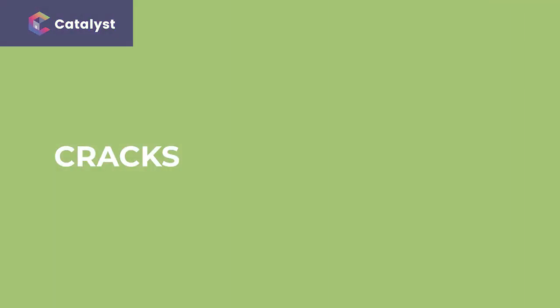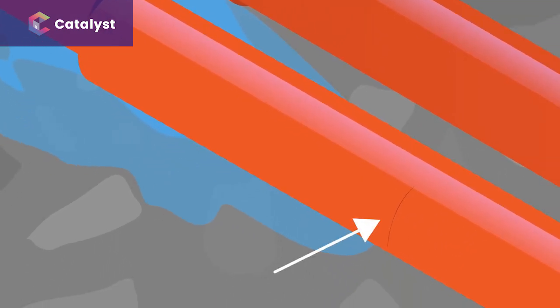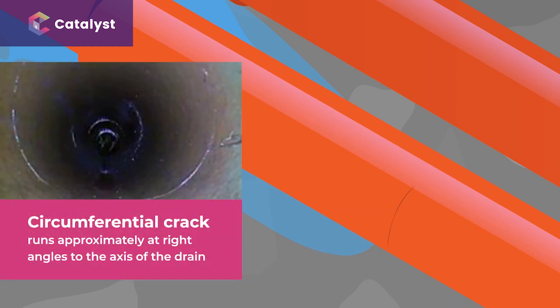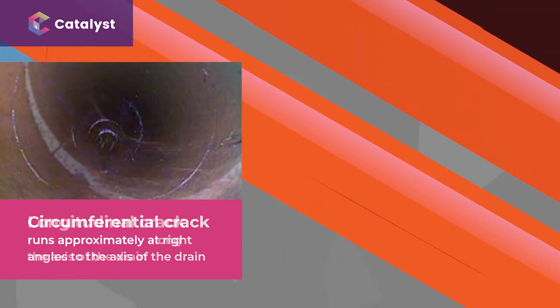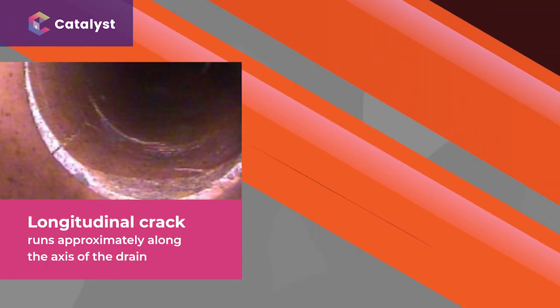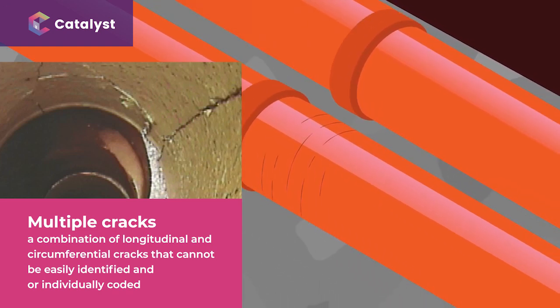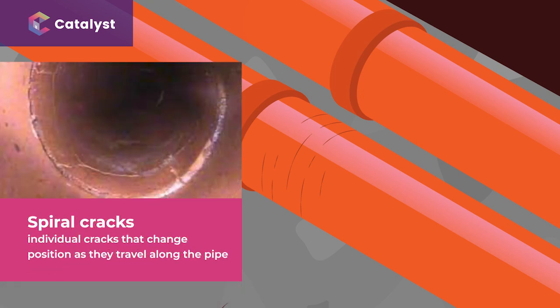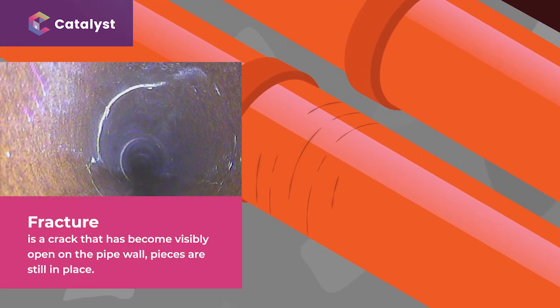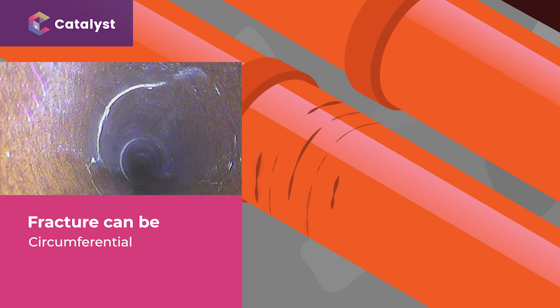Moving on to cracks. A crack is a defect in a pipe that is not visibly open — the pieces have not moved apart. A circumferential crack runs approximately at right angles to the axis of the drain or sewer. A longitudinal crack runs approximately along the axis of the drain or sewer. Multiple cracks are a combination of longitudinal and circumferential cracks that cannot be easily individually coded. Spiral cracks are individual cracks that change position as they travel along the pipe. A fracture is a crack that has become visibly open on the pipe wall, but pieces are still in place. Just as with cracks, fractures can be circumferential, longitudinal, multiple or spiral.